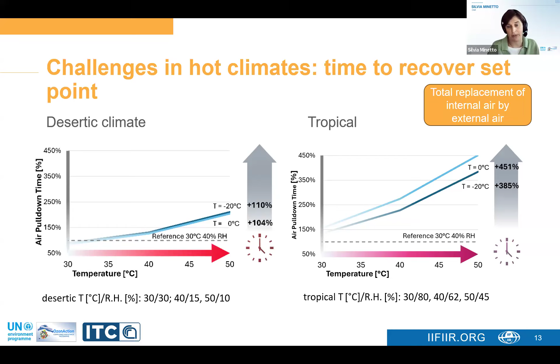But in the case of the tropical climate, which is on the right hand, the situation can become really dramatic, because it can take up to 450% longer than in the reference case to pull down the system to the initial temperature. And this means that if the unit is not correctly sized, the system might not be able to reach the set point again, and this can result in a higher internal temperature and in a large fluctuation of the product temperature. So these are the challenges, but we have also some, of course, opportunities to face.